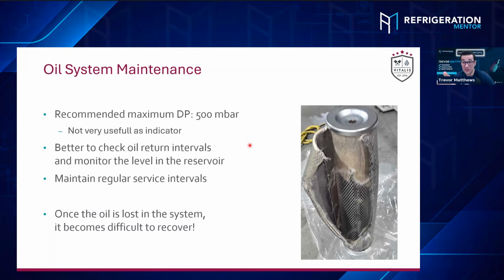Yeah. This is where real things happen. It's not that it blew, like, you had a failure in your separator. It's that it travels through the system and jams into your high pressure valve. Yes, it makes its way through. That's where issues start to happen. Yeah, big issues.